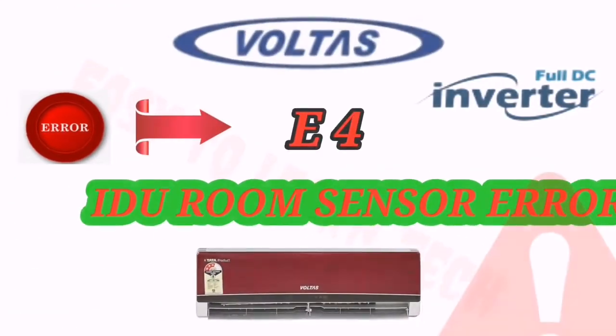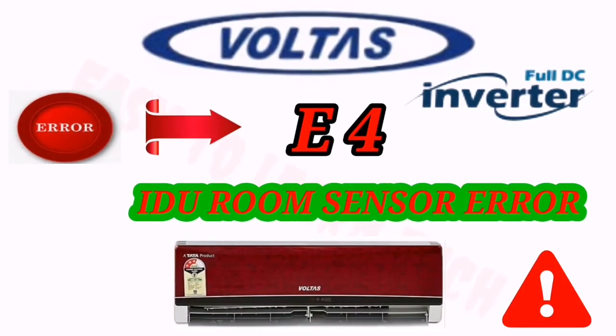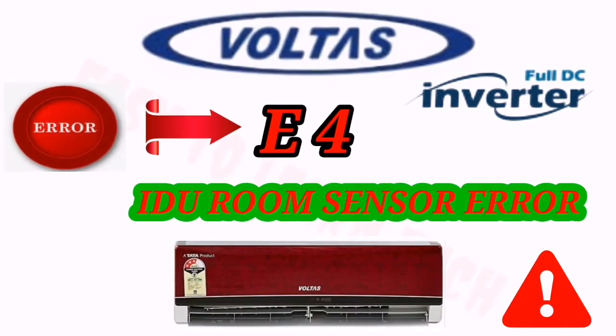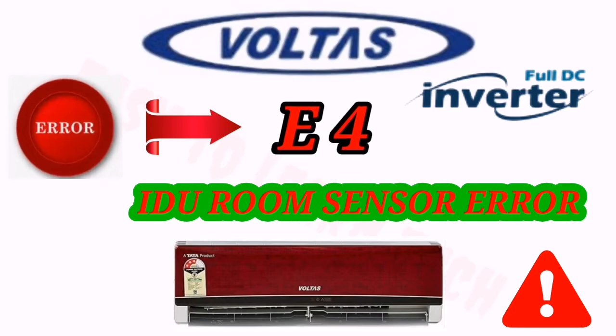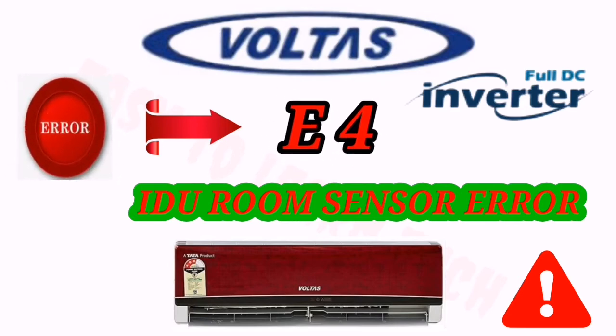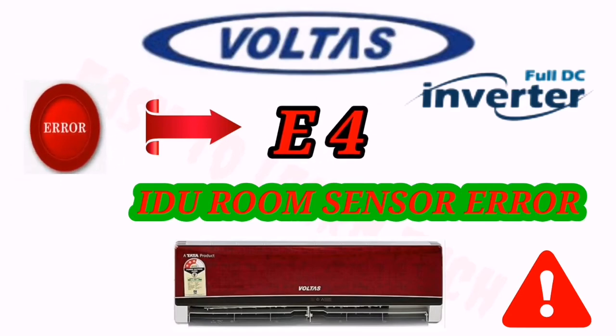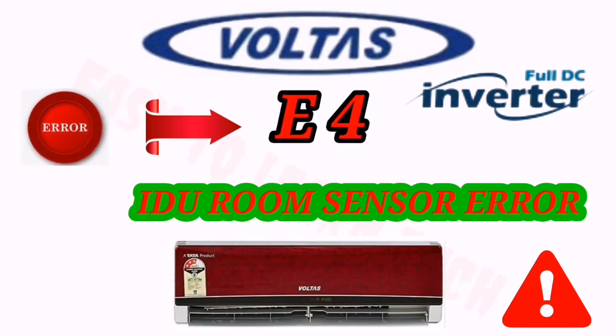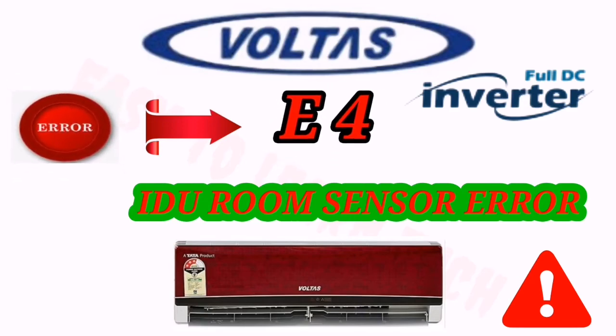Let's see the next error code. When you see E4 in your display, it means indoor room sensor error. First of all, you have to check the placement of the sensor. If the placement is not good, place it in the proper place. Then you have to check the connection. If the connection is abnormal, connect it properly to the indoor PCB and start the unit.